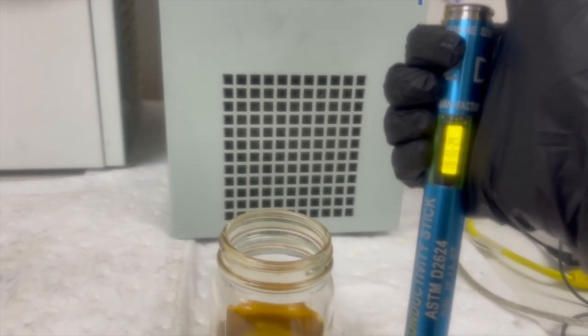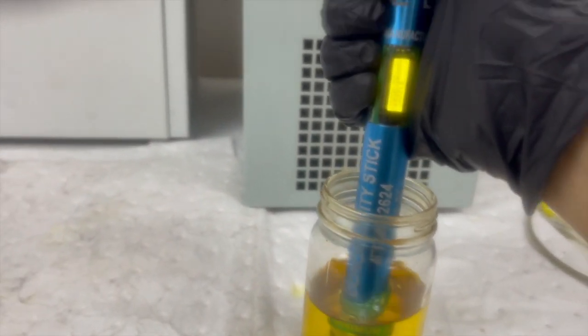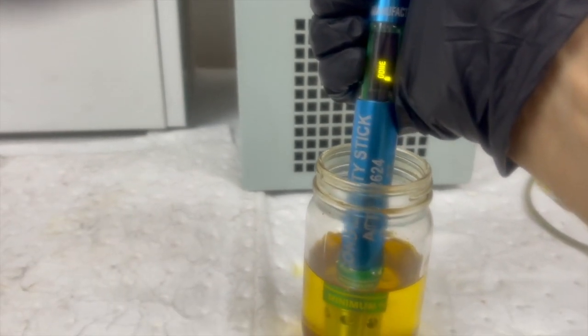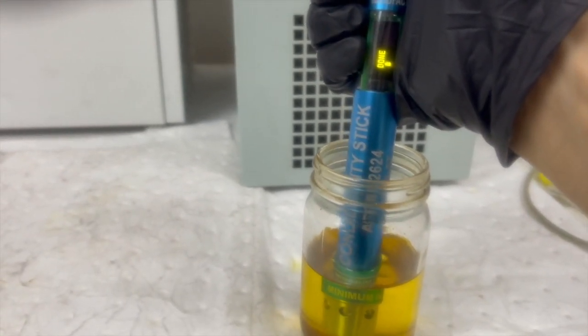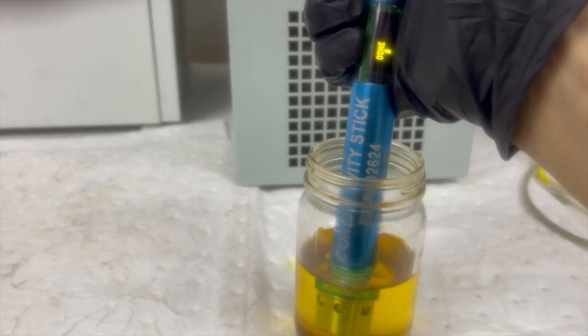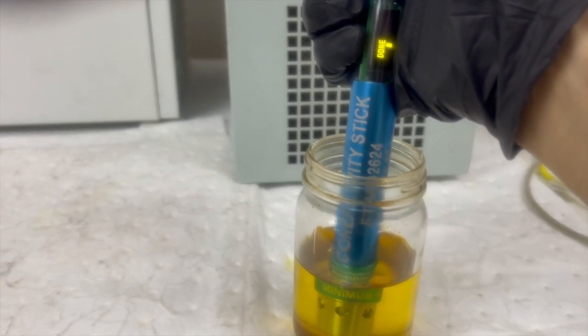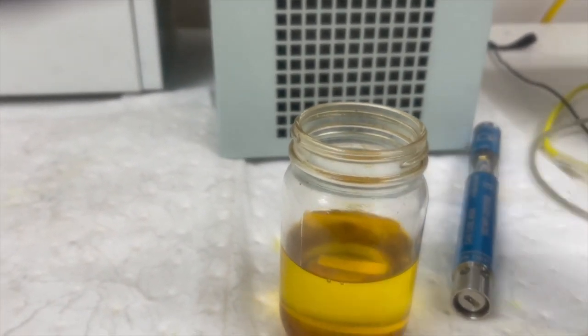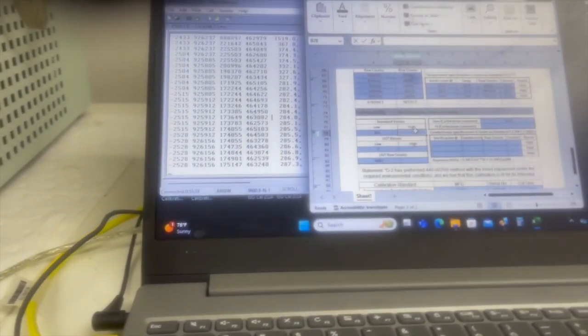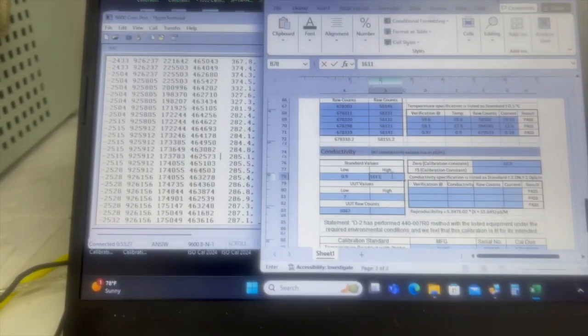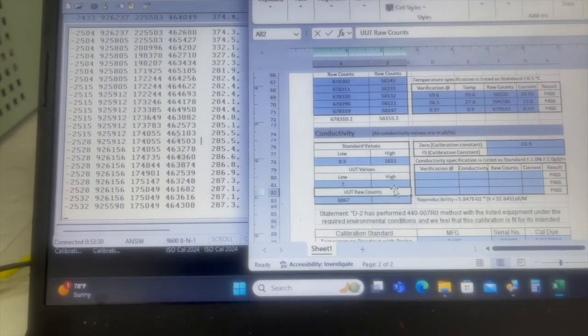okay, now we're going to get the high values for the inline sensor in order to calibrate the full range of the instrument. So we take out our trusty handheld meter, after cleaning it, of course. We're going to run it in our high sample. Get a value of 1611. I'm going to plug that in over here. 1611 for our value. And now we're going to run the inline sensor and see where it's at against that.